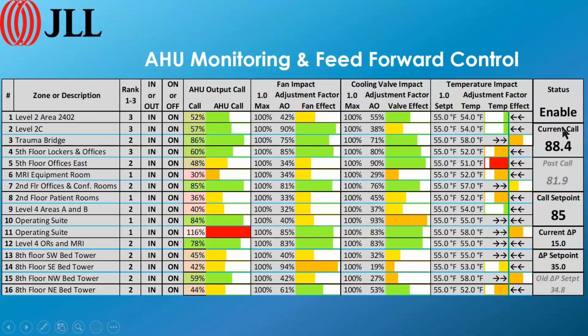That's a number between 80 and 100. It's saying right now the call set point is 85, and the current call is 88. The current delta P is 15, and the system is going to start to bump it up. In the next 15-minute window, it's going to change the delta P from 15 to probably 16. It's going to go up more. So the call set point is 85, the current call is 88. You're trying to get to 85, right? It's going to try to get to 88.